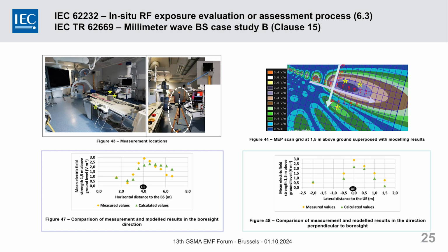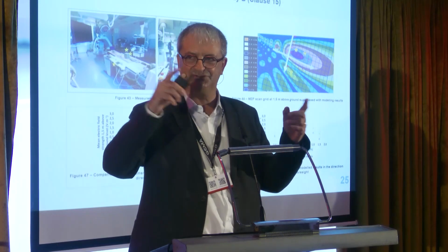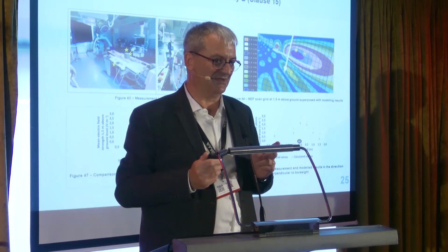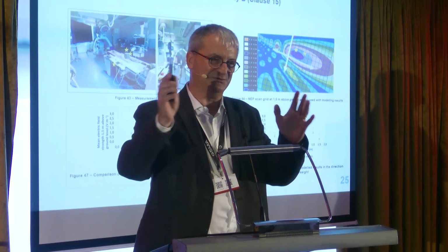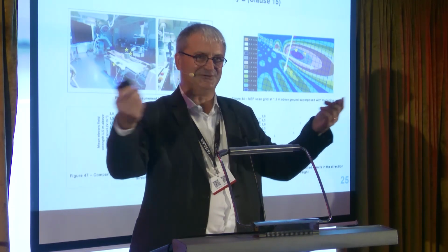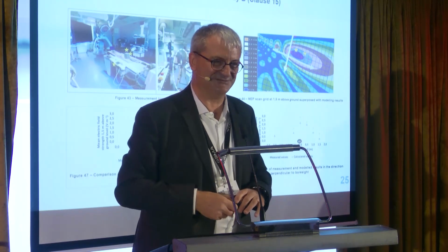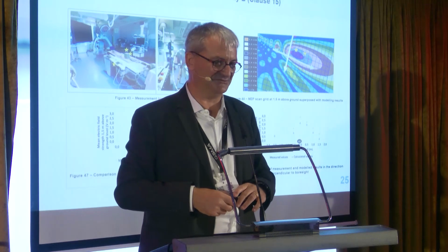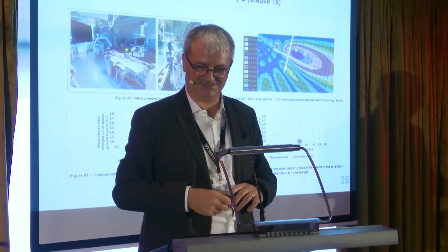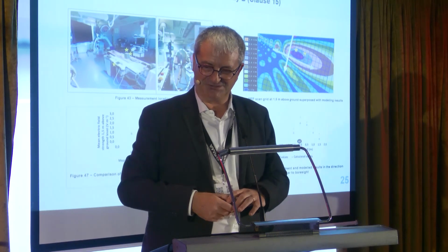So the yellow dots are measured values and the green dots are simulated values. Simulation is generally interesting, not to provide an assessment, but to show where the maxima are. It provides you an indication where you have to look instead of scanning all the room. You know approximately in which area the maximum will be, and you can go straight to that point and do the assessment and take the spatial averaging part.